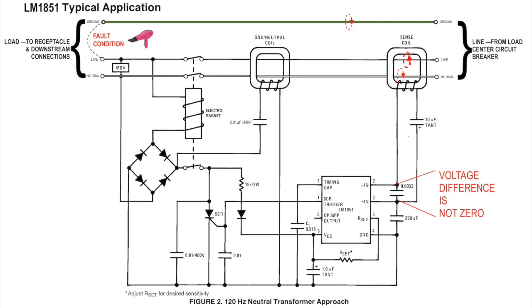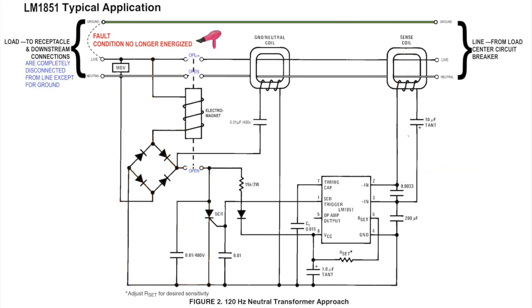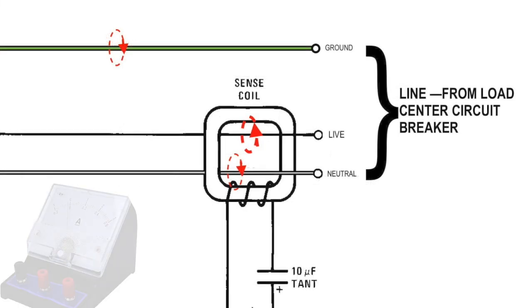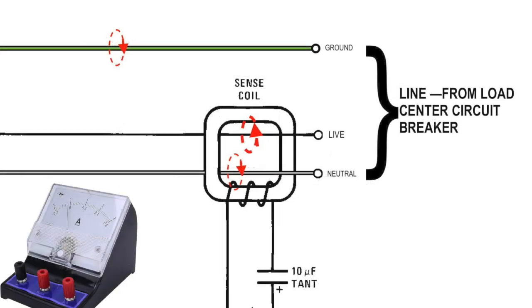If that happens, more current is flowing on the live conductor than on the neutral conductor. Inside the differential transformer, the currents on the live and neutral are no longer equal and opposite. The difference between them is detected by a comparator, which amplifies the difference and sends a signal to a silicon-controlled rectifier to activate the solenoid, killing the power to the whole circuit and to the hairdryer, and possibly saving your life if you happen to be touching it at the time. This will happen with only a few milliamps of difference between live and neutral.